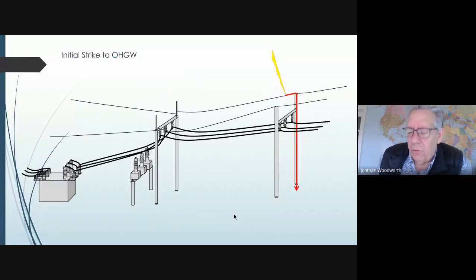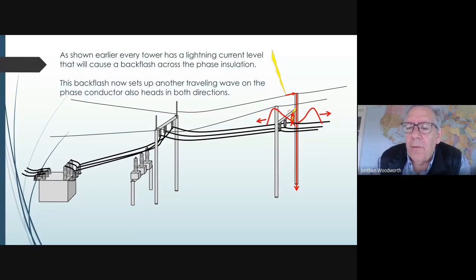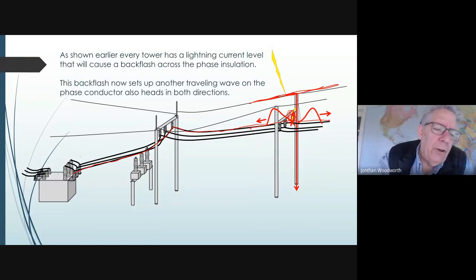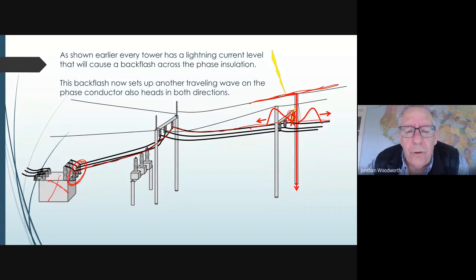Sometimes, as I showed a second ago, lightning will strike the system, and then we'll have a backflash on the insulator. And when we have a backflash on the insulator, now the surge that was also going down the shield wire is now going down the phase conductor. And that goes right down the phase conductor, right into the substation. And when it gets into the substation, if we don't have arrestors right here, we have a dead transformer. So this is how lightning gets into a substation.